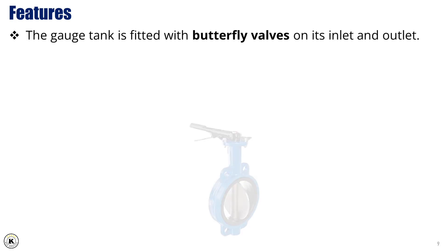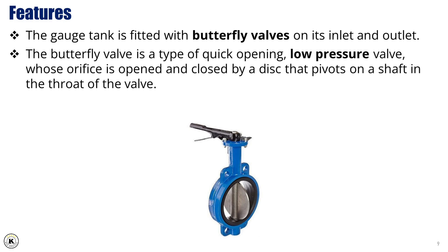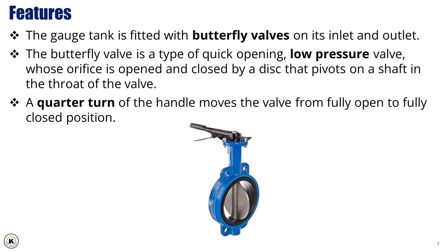The gauge tank is fitted with butterfly valves on both its inlet and outlet. The butterfly valve is a type of quick-opening, low-pressure valve. Its orifice is opened and closed by a disc that pivots on a shaft positioned in the throat of the valve. With just a quarter turn of the handle, the valve moves from a fully open to a fully closed position, making butterfly valves ideal for fast and efficient flow control, especially in well-testing setups where quick response is essential.